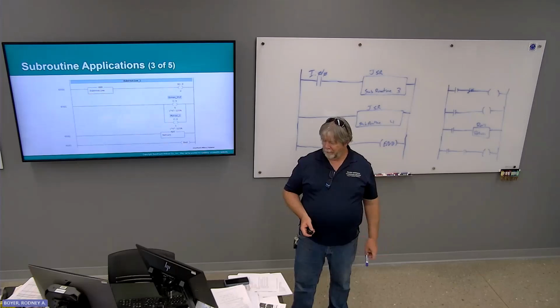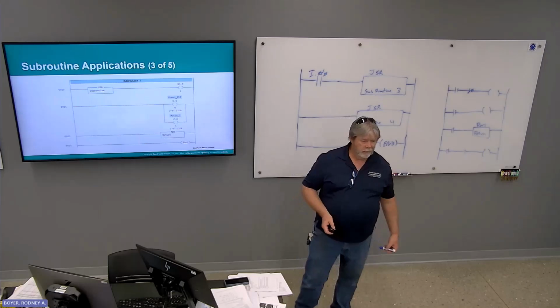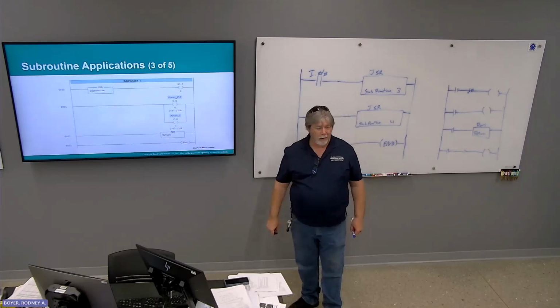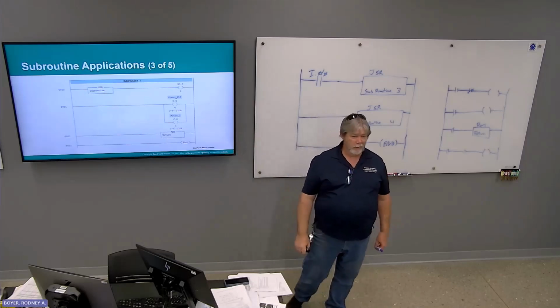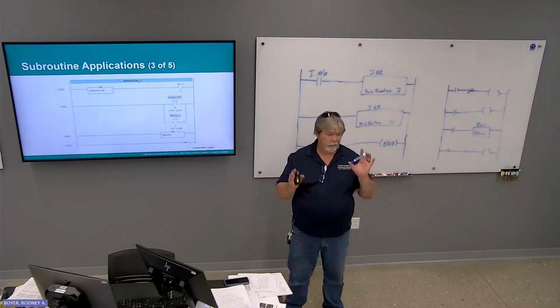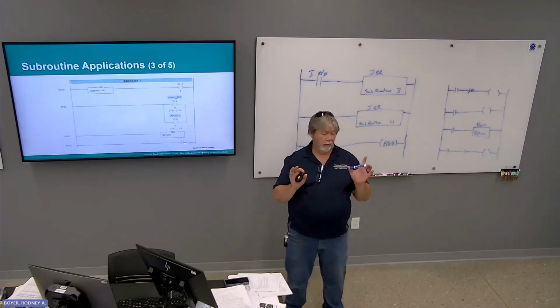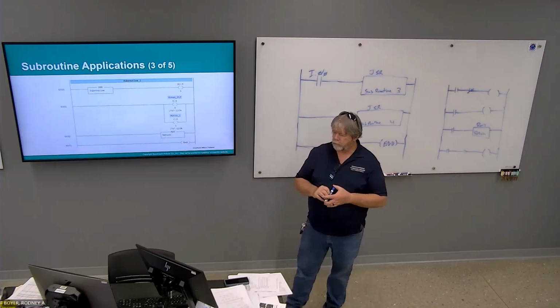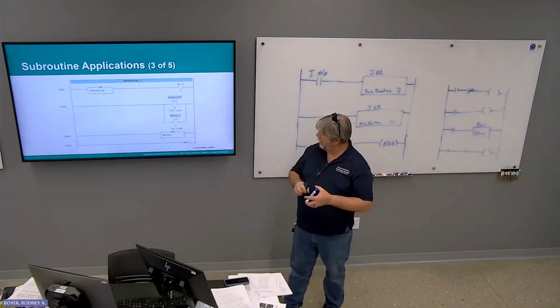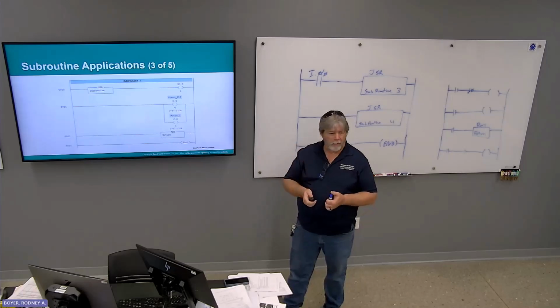So in the subroutine, there it shows the SBR subroutine instruction, and then there's that B30, which is just a dummy bit, because SBR is an input instruction. You must have an output on every rung. So it's not doing anything but saying, hey, there's an output here. So it will unconditionally turn on the green pilot, motor 1, and return back to the main. Okay.